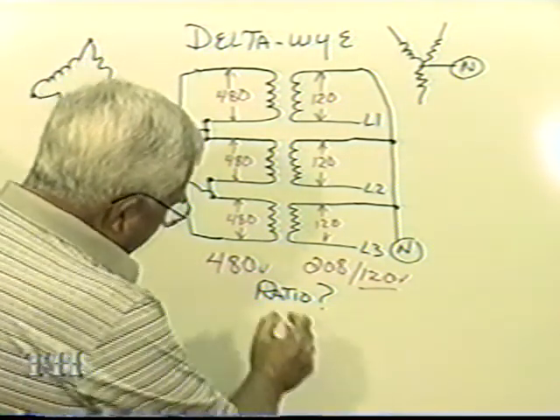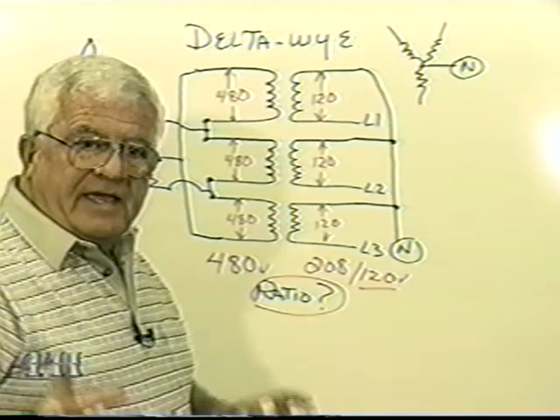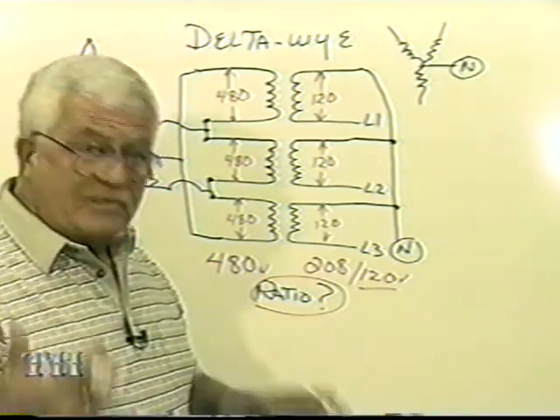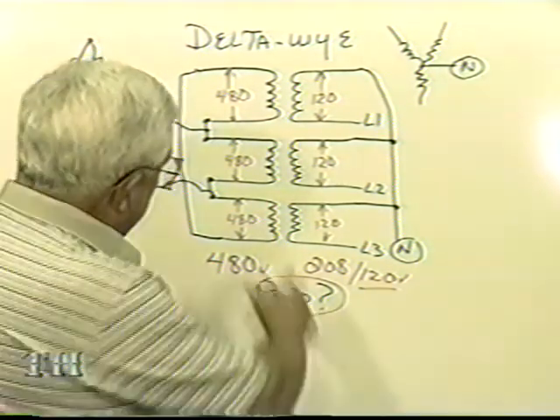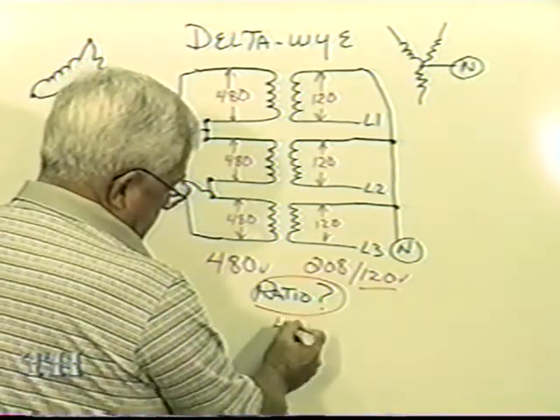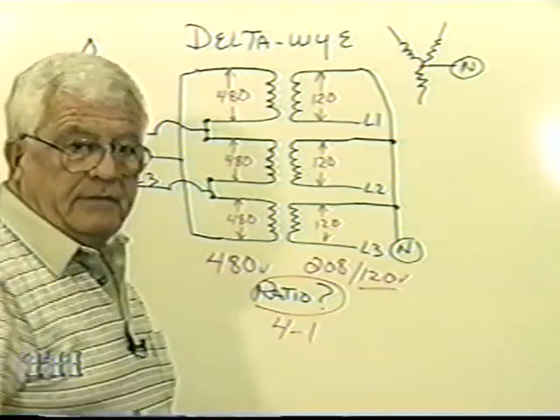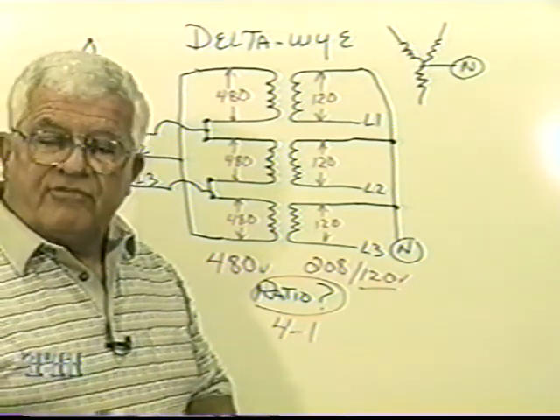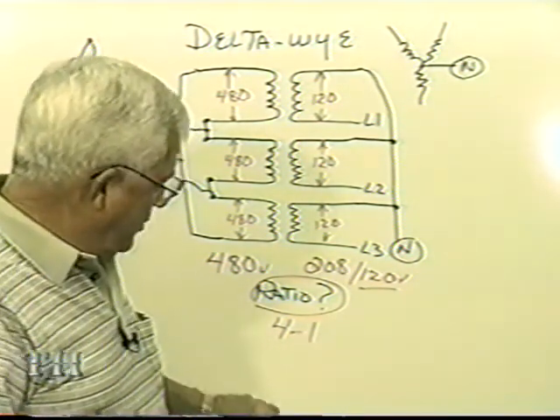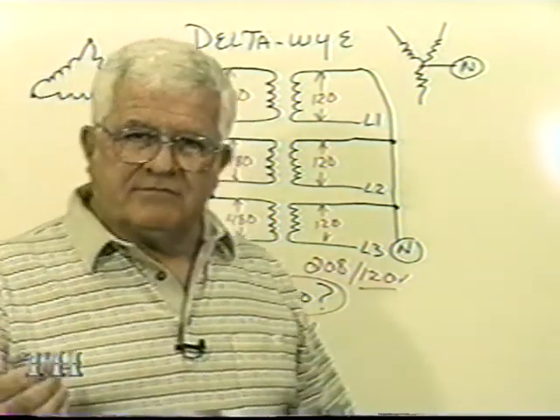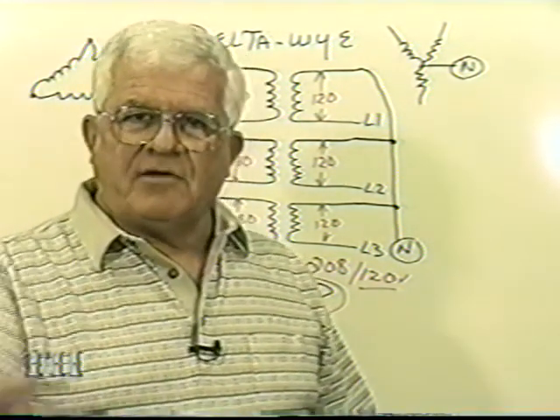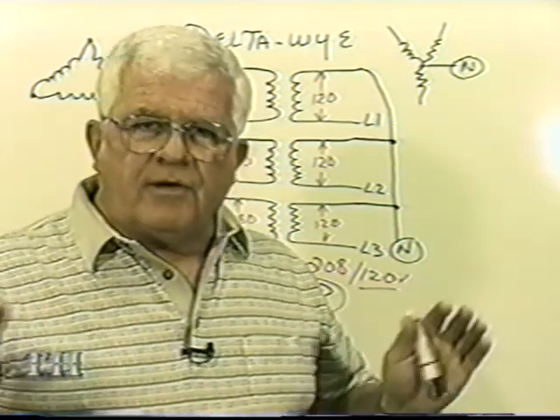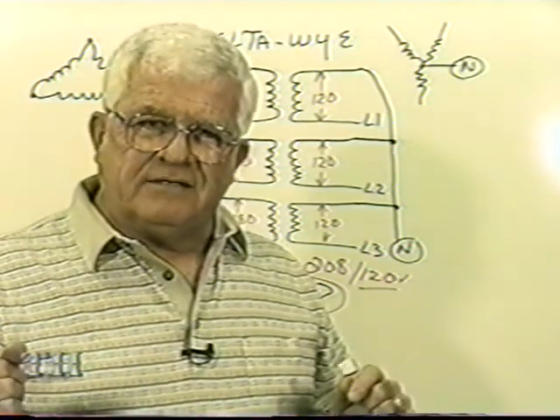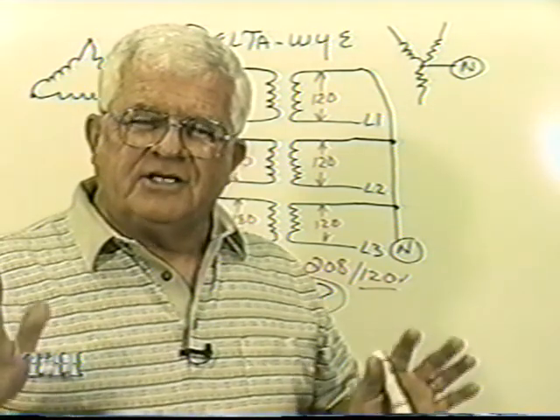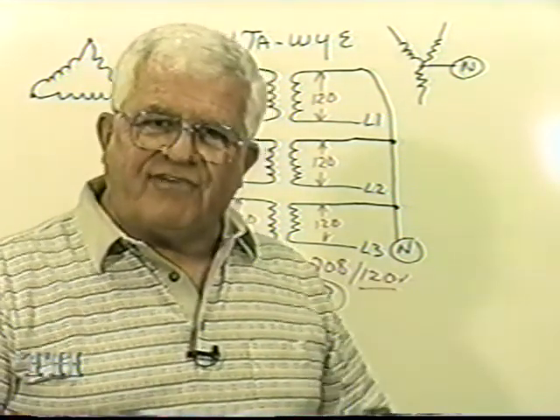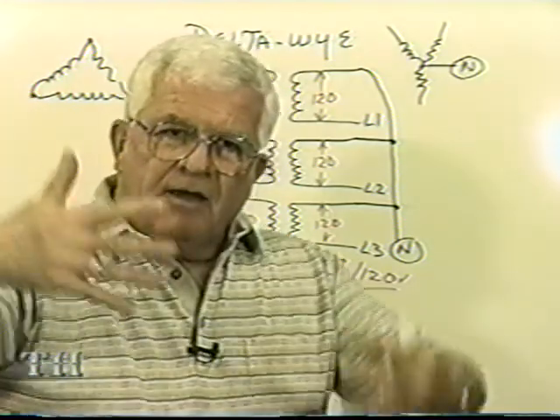Now watch, you come back to the question they ask you on the exam, and they say, what's the ratio? Well, that's easy: 4 to 1. Coil to coil, phase to phase, that's your ratio. You can't believe in my travels how many get that wrong. Oh, they want to take 480 volts and divide it by 208 for a ratio. Wait a minute, 208 is a line voltage, it's not a phase voltage. That's out there, we got to stay down here.